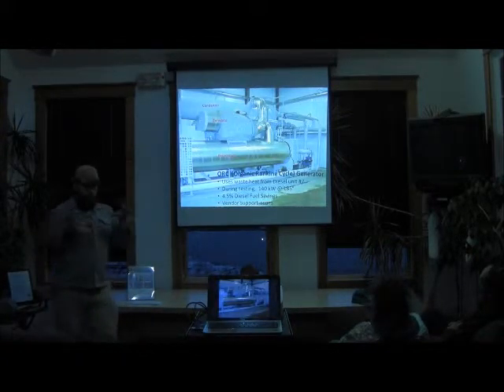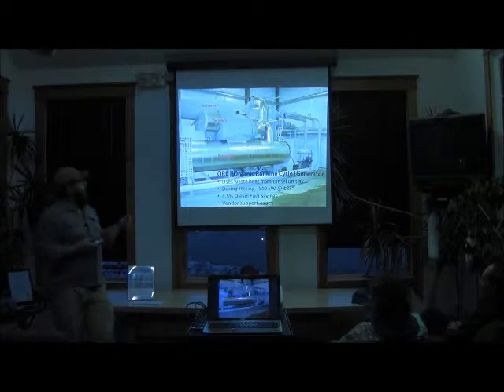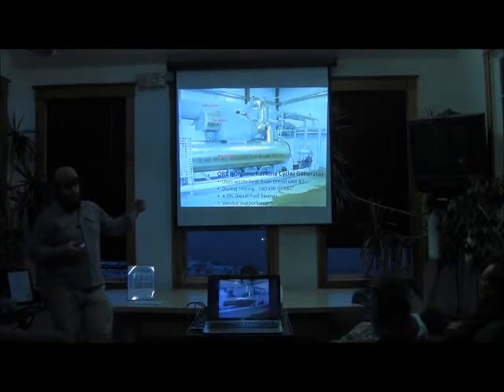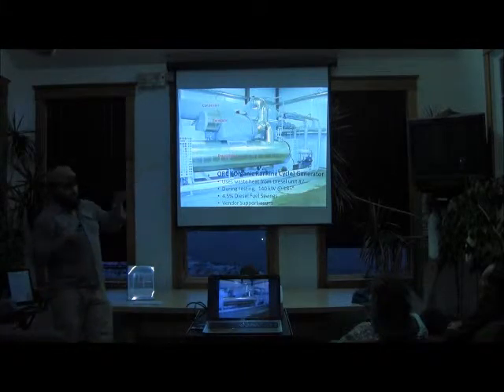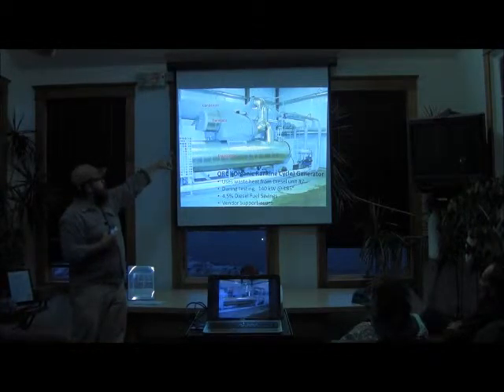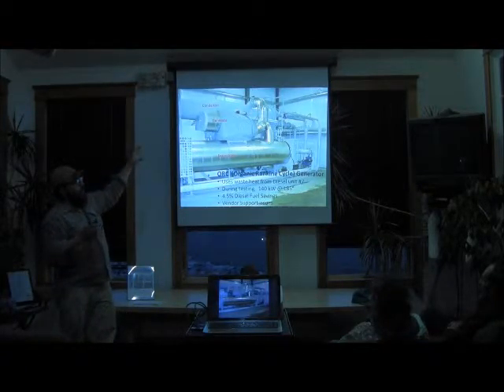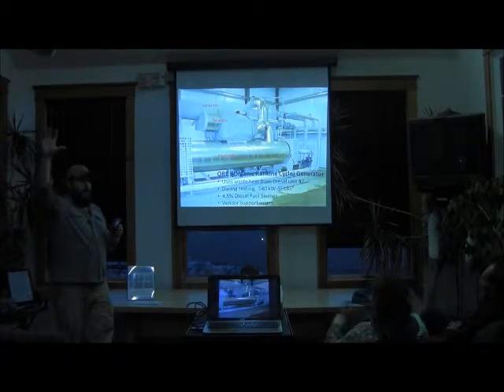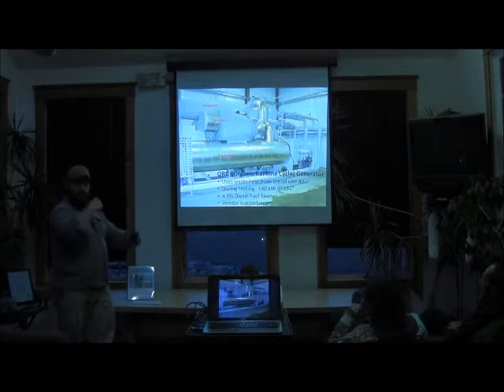Basically the diesel engine's running like a car engine. That hot water, the cooling water going through the engine, that we normally run out to the radiator, and all that heat is just blown off into the atmosphere. We're bypassing that and running that heated coolant into this bottom tube, the evaporator. In the evaporator, there's a heat exchanger with a glycol solution that the water flashes off. Since it flashes at a much lower temperature, it basically turns to steam, goes through the generator, spins a turbine, and powers a generator, and then goes back into the condenser. If you drive by the power plant, you'll see a big cooling tower in the back. That's where we're sending cool water in to cool down that glycol solution to send it back to the evaporator and keep that cycle going.